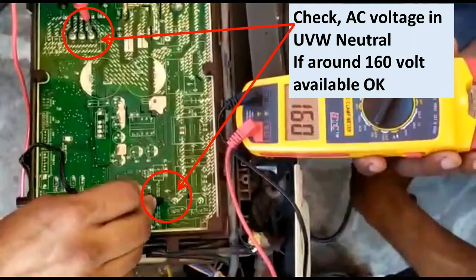Then we can also measure the AC voltage. For checking the AC voltage, we have to place one probe on the neutral and the other probe on U, V and W, and we will get the same voltage here. So in this manner we can check all the points at the PCB.